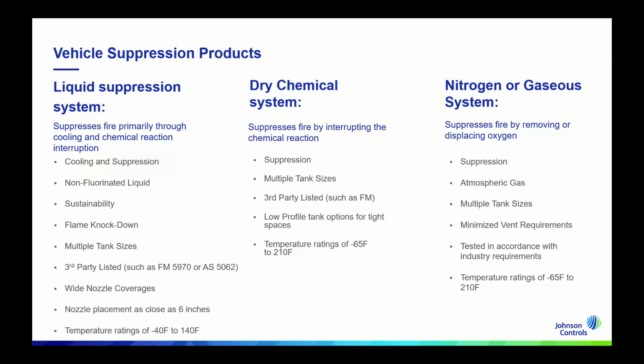It's important, when you're looking at a gaseous system, right, to look for an atmospheric gas that meets sustainability requirements. Even with gaseous systems, there can be multiple tank sizes to vary the amount of agent that's delivered. You want to be able to minimize any venting requirements. So with gaseous systems, we displace oxygen by putting more volume of gas into an enclosure. So being able to vent and not overpressurize an enclosure is important. Looking for something that's tested in accordance with industry requirements, and then like across all the other ones, right, that wide temperature rating. As we know, sometimes mobile equipment gets moved all over the world.